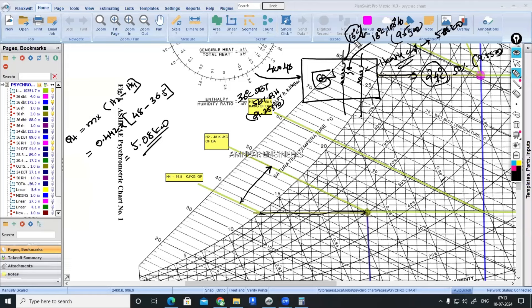So when the air is leaving the heating coil, since the temperature has increased from 13°C to 24°C for the same humidity ratio, the condition will be 24°C at 50% relative humidity. Whether the heating coil is required or not is conditional — it depends on the climate condition. In the original question, mixing alone can achieve the target. But in a real scenario where from the machine outlet itself you need 24°C at 50%RH, after the cooling coil you must provide a heating coil as well.